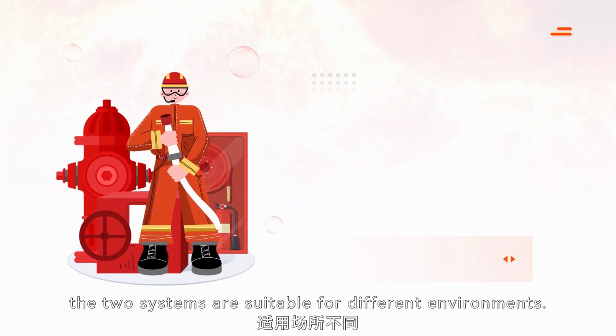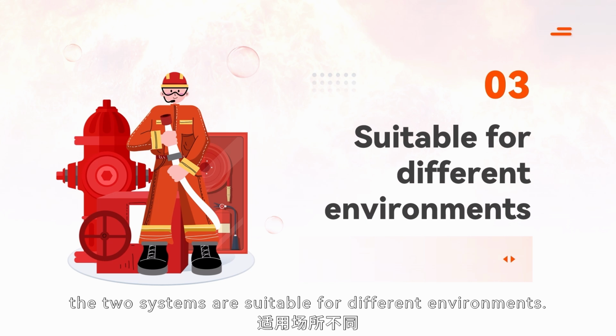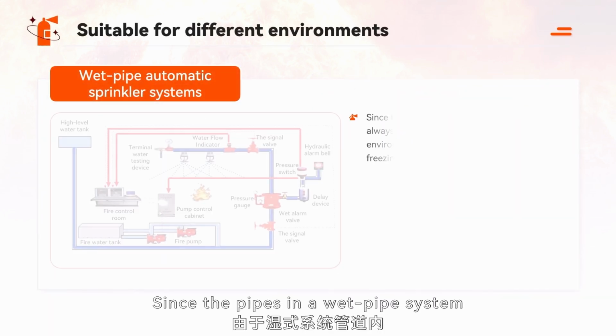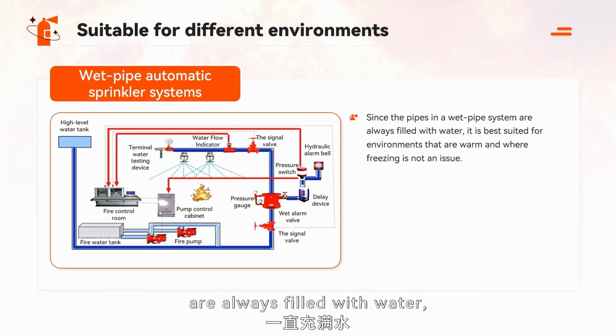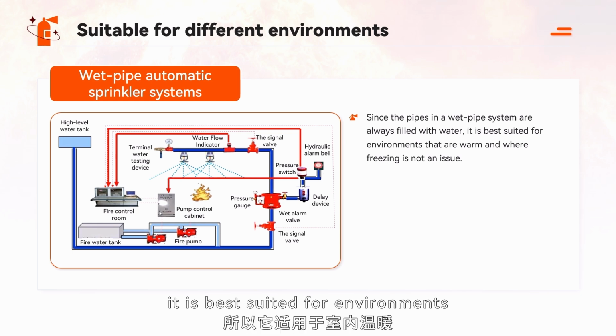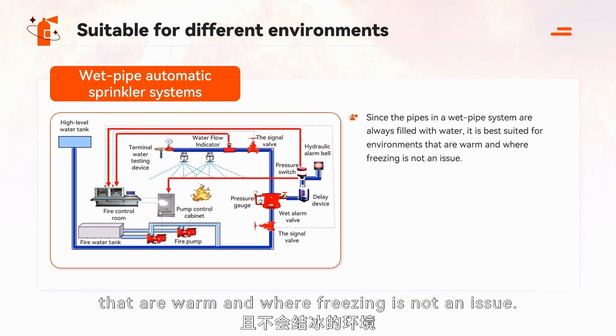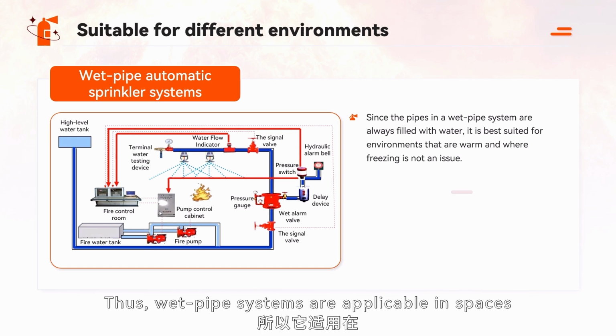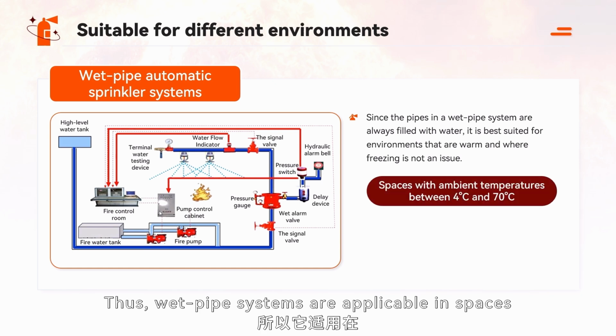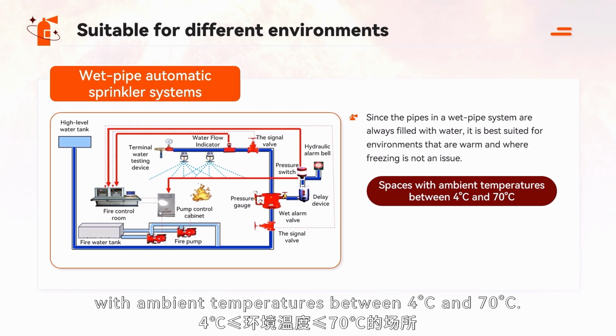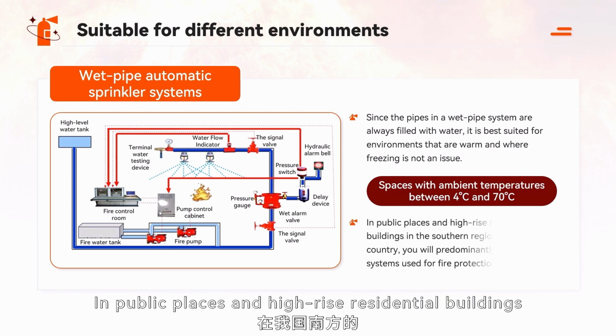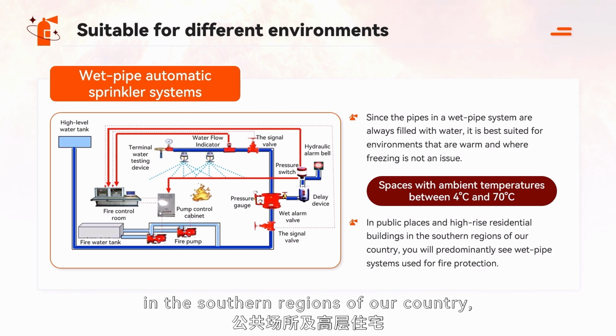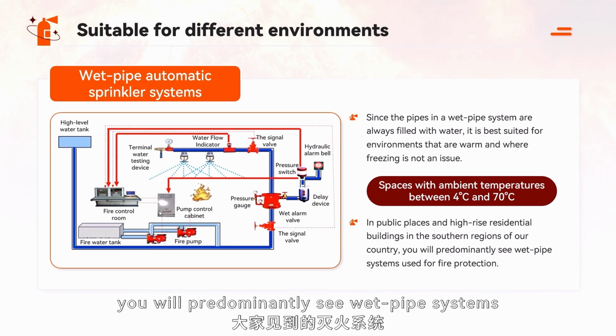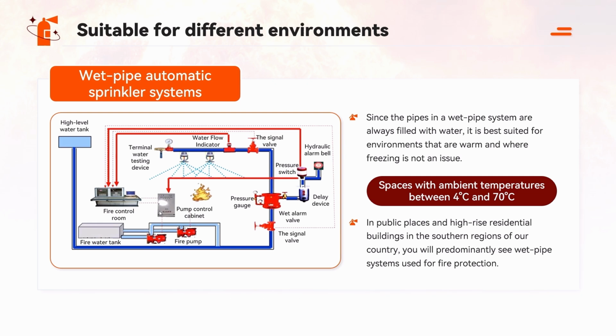Third, the two systems are suitable for different environments. Since the pipes in a wet pipe system are always filled with water, it is best suited for environments that are warm and where freezing is not an issue. Thus, wet pipe systems are applicable in spaces with ambient temperatures between 4 degrees Celsius and 70 degrees Celsius. In public places and high-rise residential buildings in the southern regions of our country, you will predominantly see wet pipe systems used for fire protection.